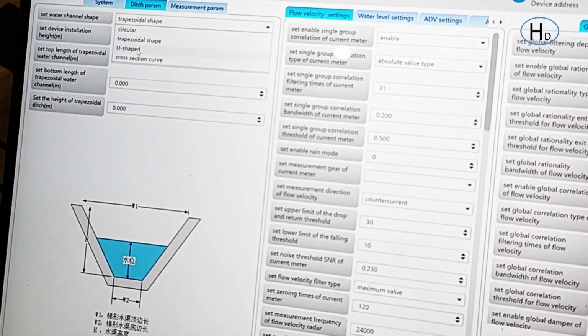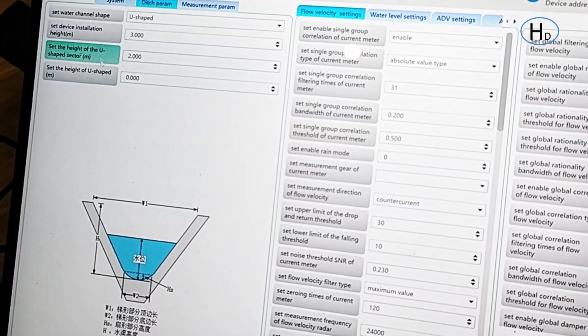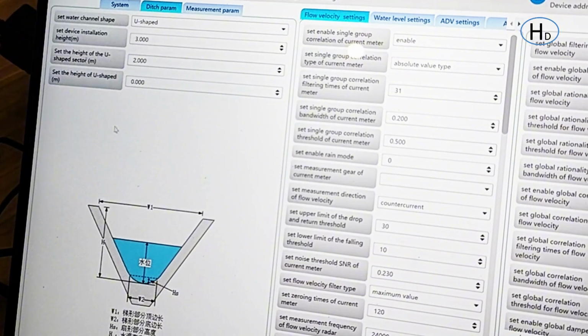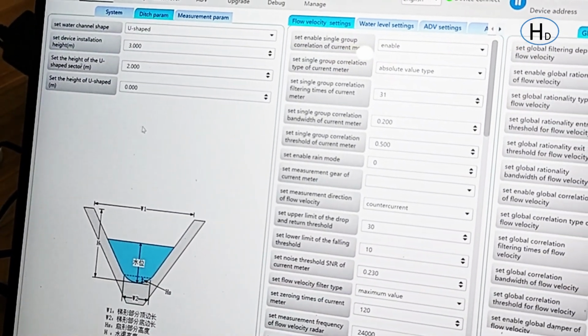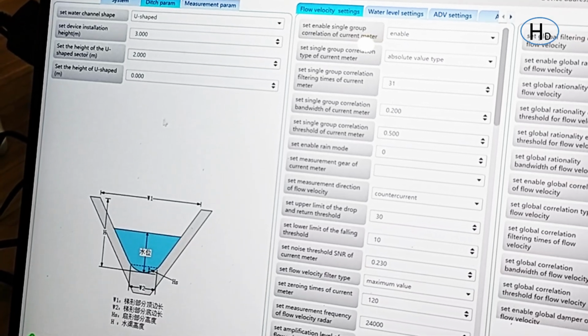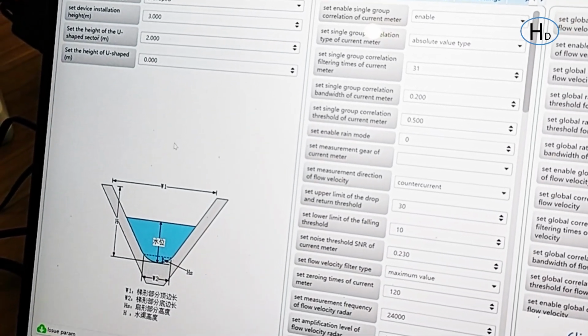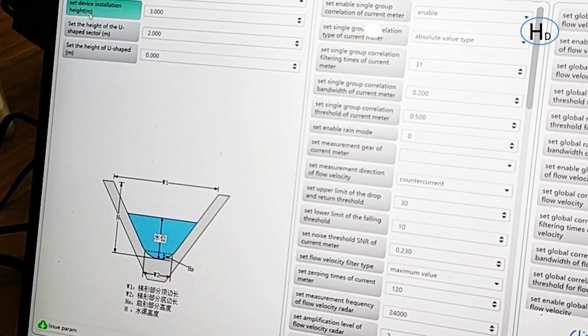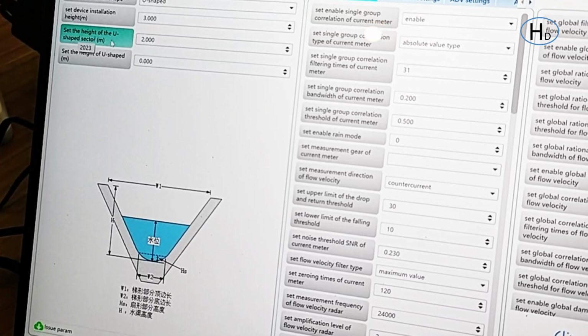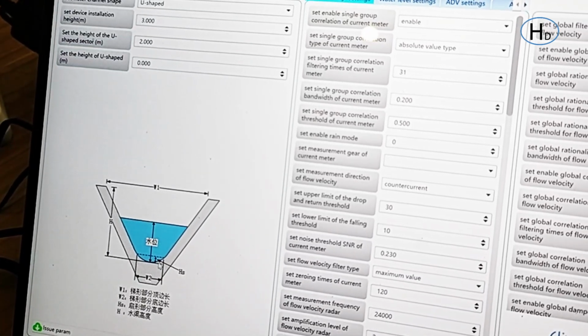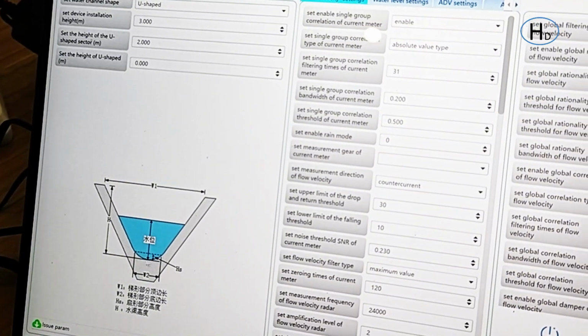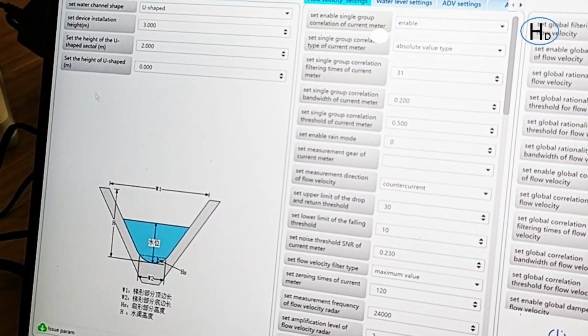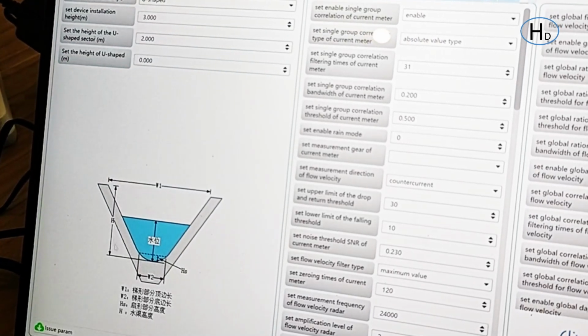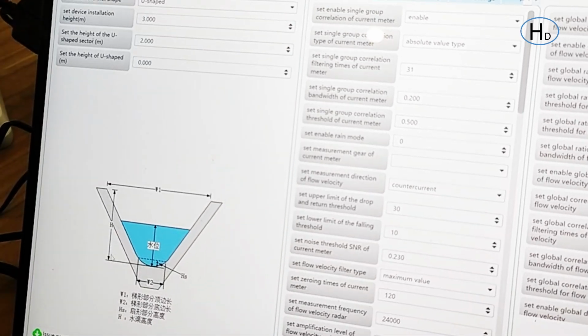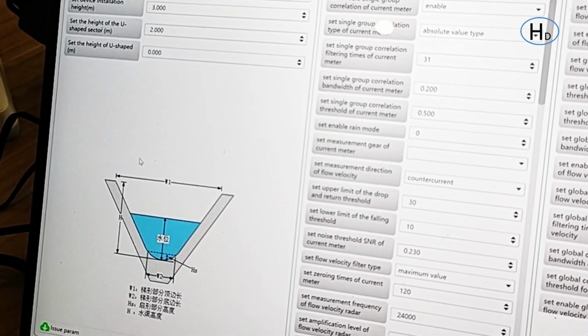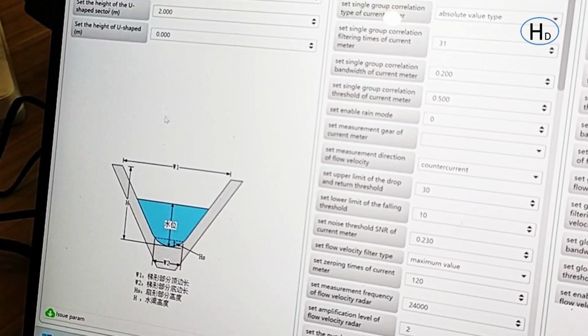And the last one is if you use a U-shape, then you also set the device installation height. That means, for example, you install here, and you need to set the height from here to the bottom, and the unit is meter. And second, set the height of the U-shaped sector, and that means HS. You need to set this one. And third, set the height of the U-shape, you set here. That is this one, H. And after you set these parameters, then it will calculate all of the water flow directly.